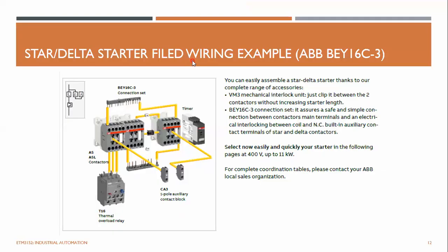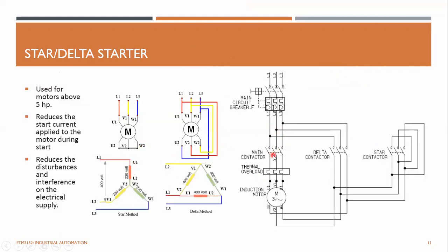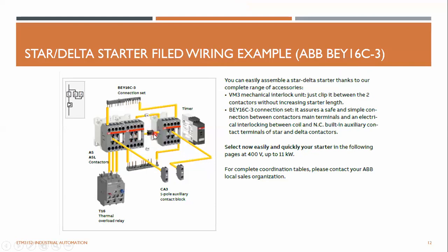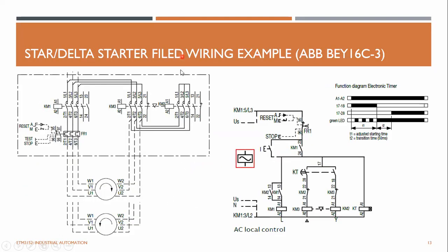Okay, now this is a field wiring example with the ABB BEY16C3 series. So you have your main contactor, and you have your star delta connections, and they are interlocked. And this is the timer that I'm talking about, right? So with the timer, you can adjust the timing. You can set the time for making the star delta connection, and finally it goes to the thermal overload relay, and then goes to the motor. Okay, this is the final wiring diagram.